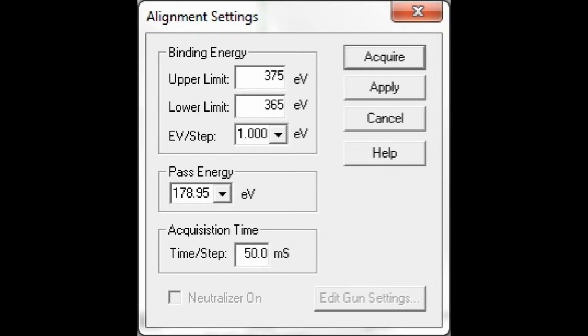If you have a standard 15 kV dual source, you're going to use that for the procedure because it has a larger excitation area than the mono source. You bring the source down to where it starts to block the microscope TV image, like it is here, it's shadowed. So we'll move the sample around a little bit here and zoom up a little so you can see what this looks like with the TV image.